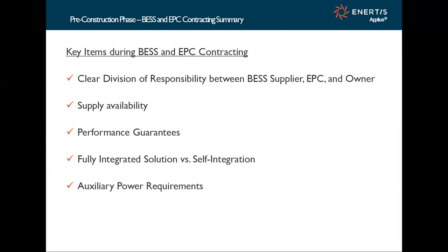The last piece, a mix between the pre-construction and construction phases, is aux power. When these containers arrive on site, they need to be in an environmentally cooled environment depending on where your project's located. Aux power may be relatively low when batteries are idle, but there's a lot of congestion on the distribution system no matter where you're at in the U.S. So engage the distribution company early on to understand what load is needed for both idle periods and peak periods when batteries are charging or discharging.